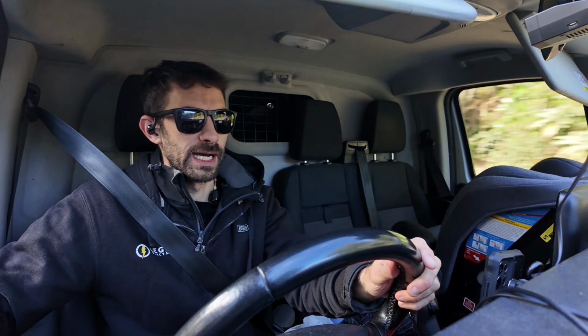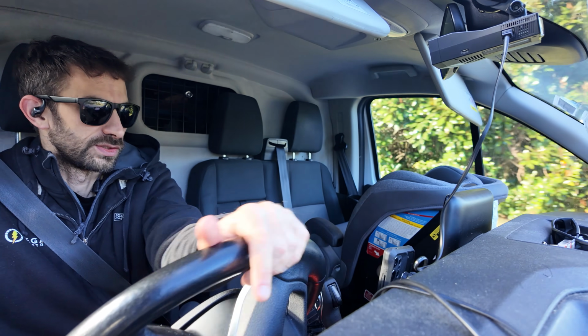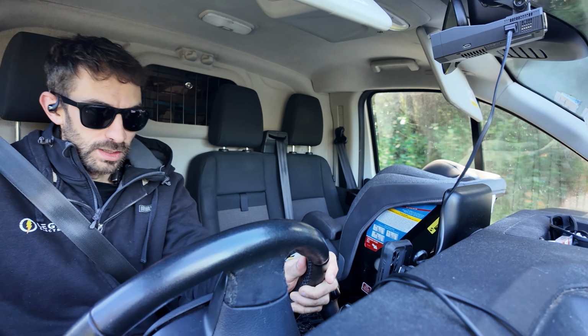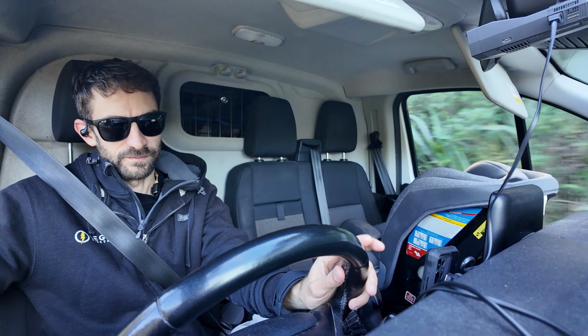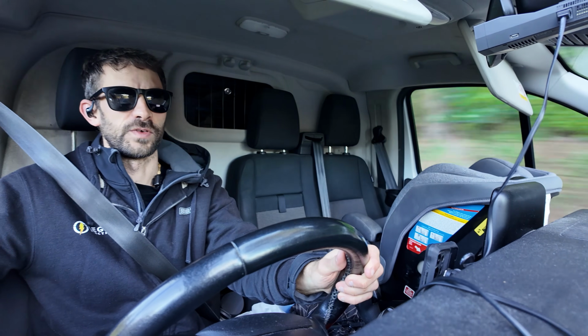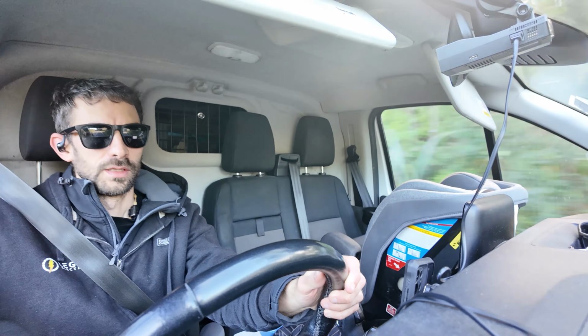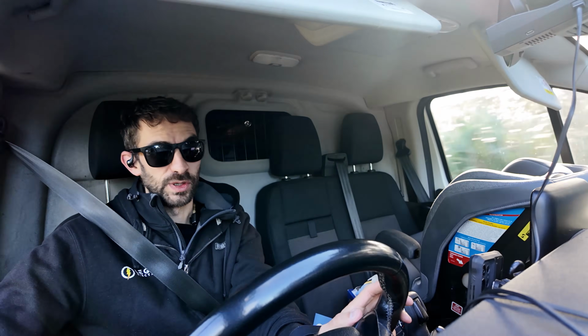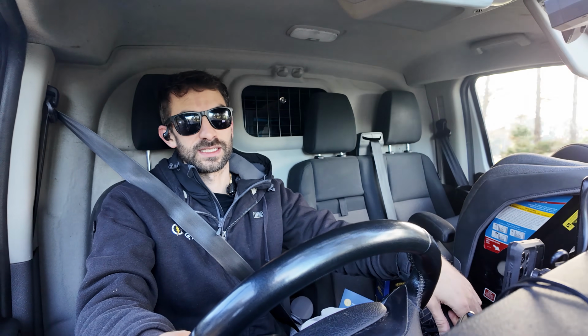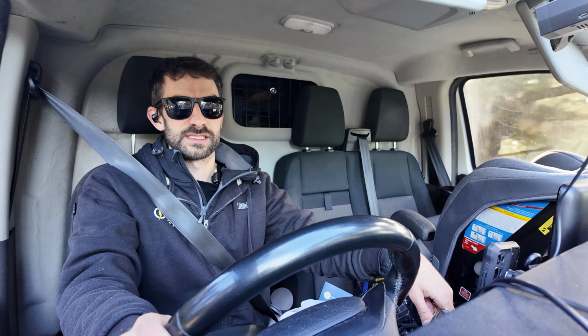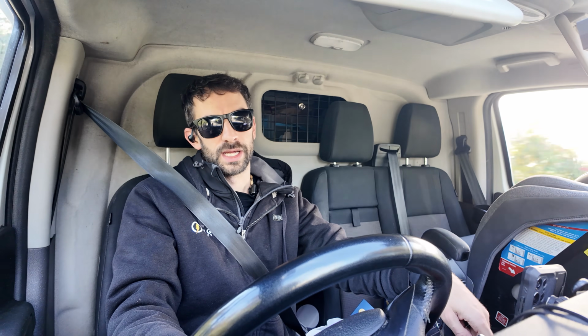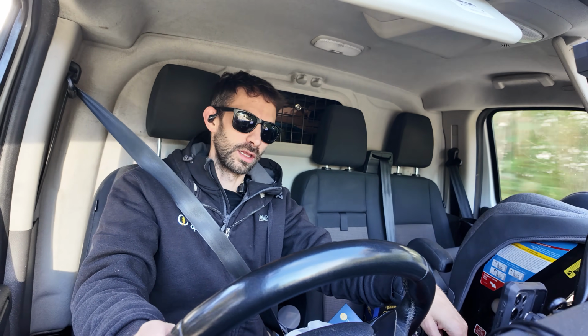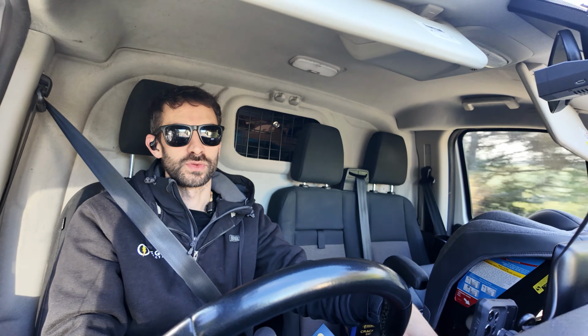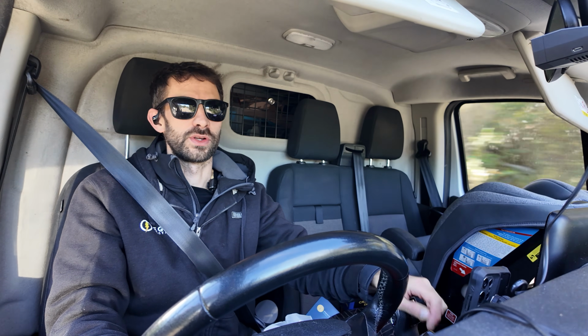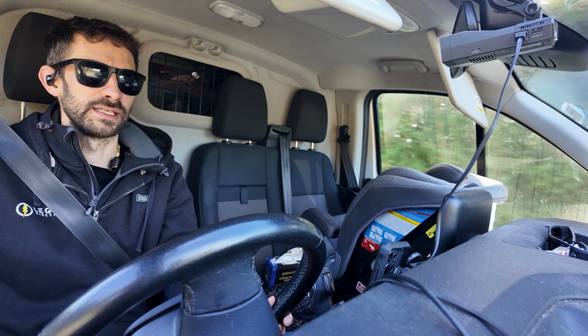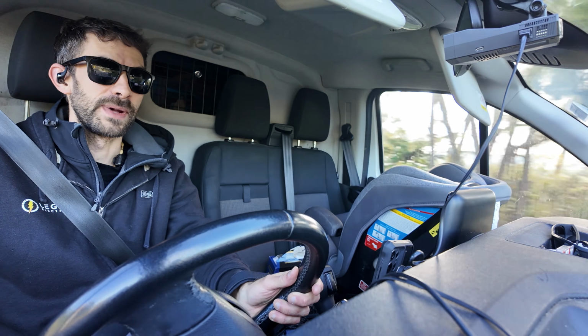So the earth electrode can't protect you against a loss of neutral fault, even with RCDs, because the way it works is to get voltage on your earthing system from a loss of neutral fault, you need to have loads connected. Those loads are connected either through an RCD or not. If they are connected through an RCD, the current path to build up that voltage runs through the phase conductor of the RCD, through the load of the appliance, and back out through the neutral again. And then you get the other end of it on the earth conductor. So if you touch it and get a shock, the current is flowing through the RCD without creating an imbalance, so it won't trip.